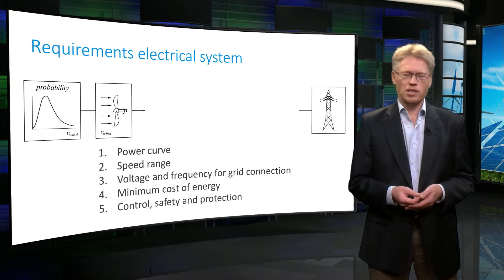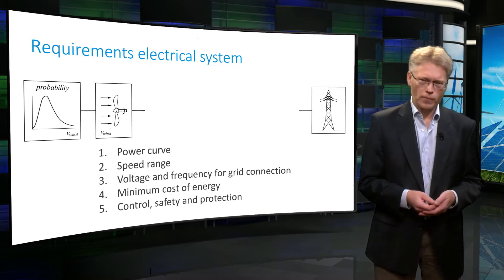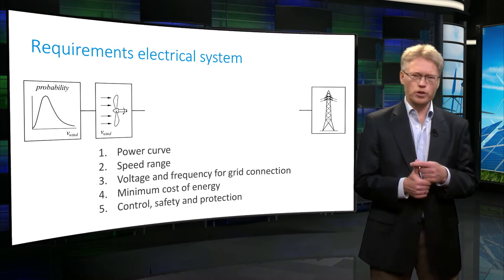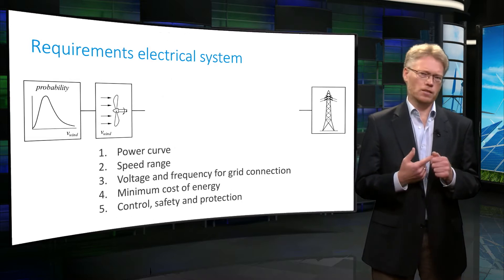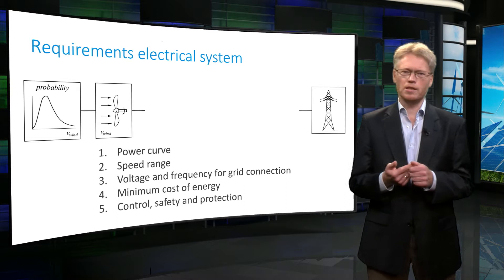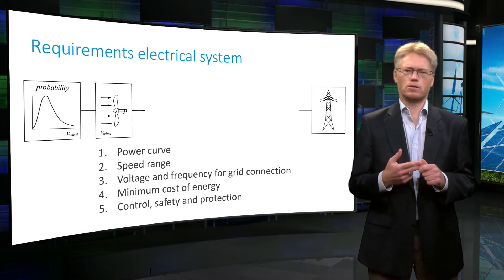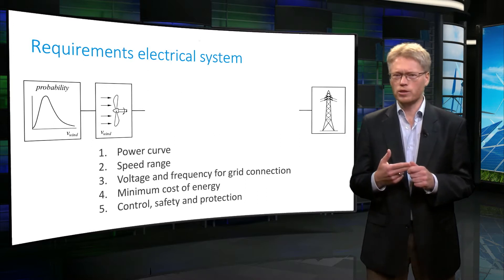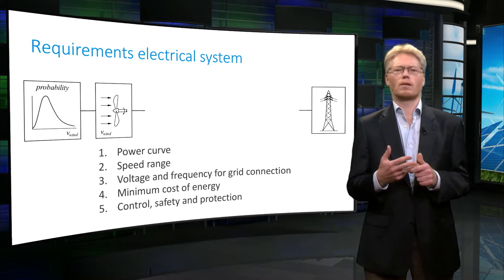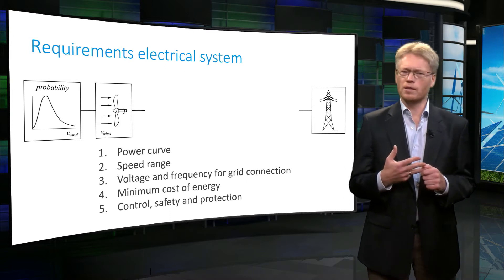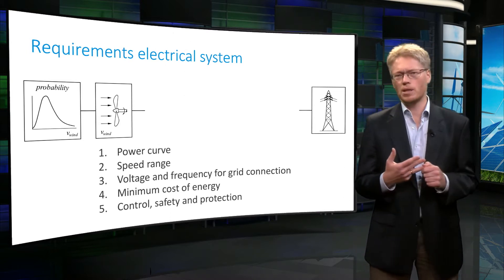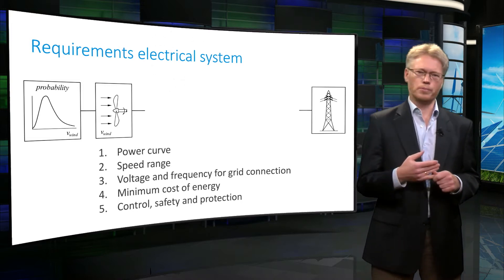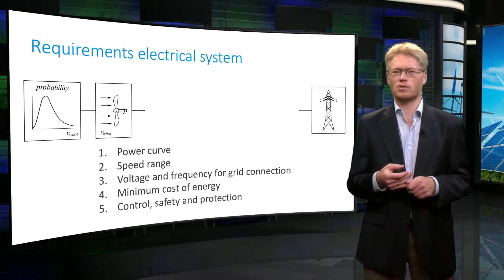What are the requirements of the electric system that makes this connection? First, the turbine has a power curve and that power must be converted into electrical power. Second, the system has to operate at a varying speed. Third, the power has to be supplied to the power system at a voltage and frequency of that power system. Fourth, this has to be done in a cost effective way, minimizing the cost of energy. Fifth, there are all kinds of control, protection and safety systems around this.